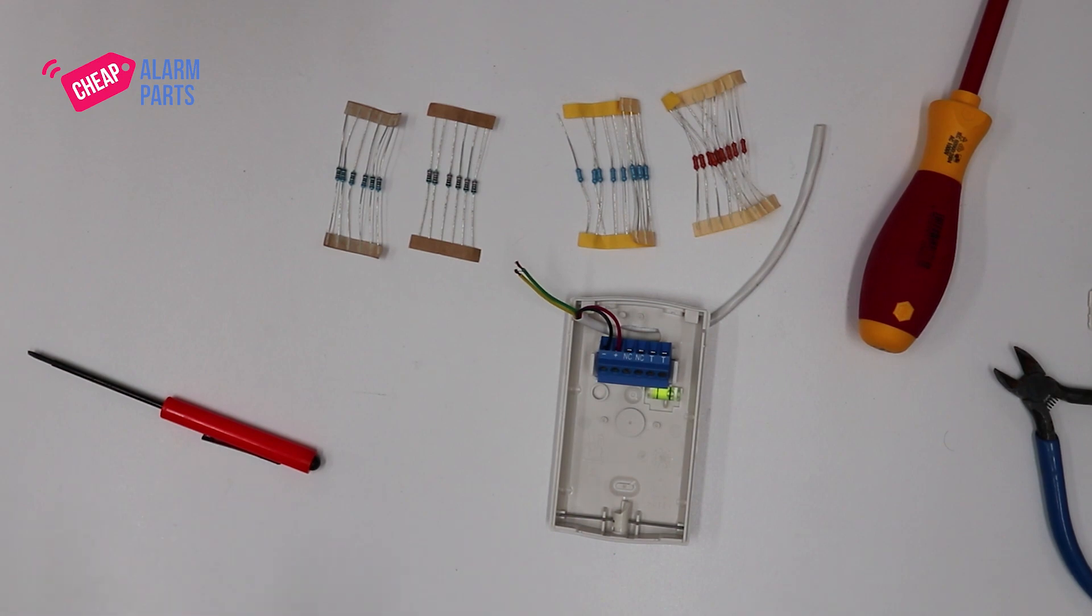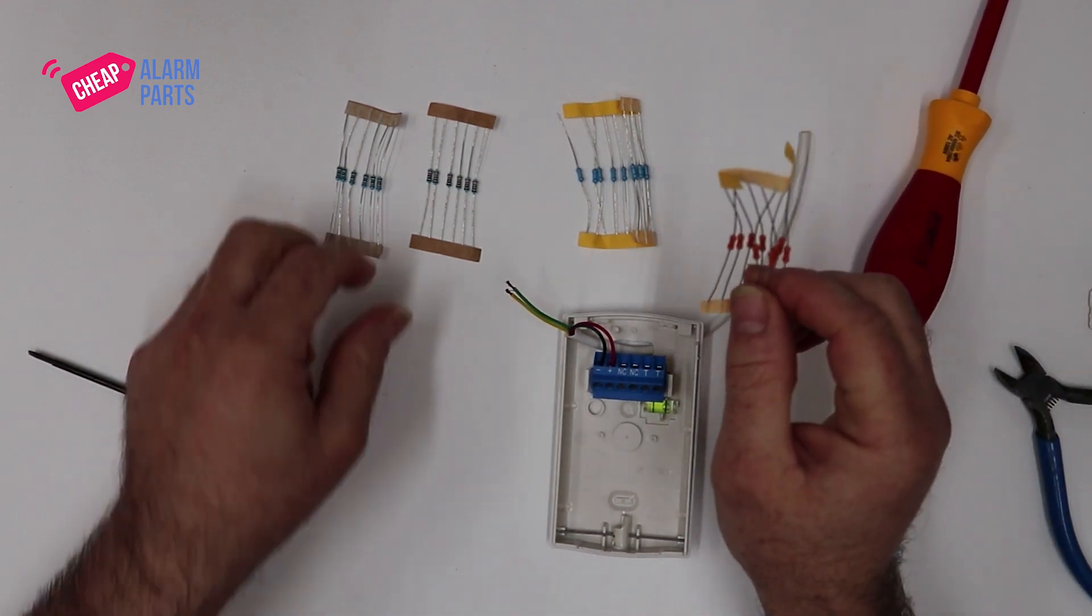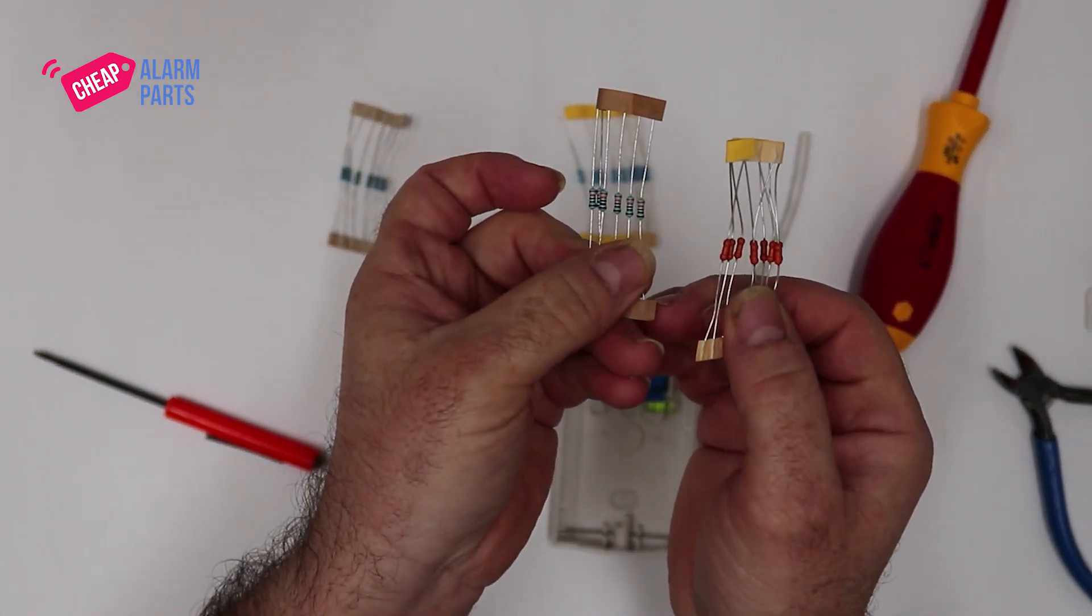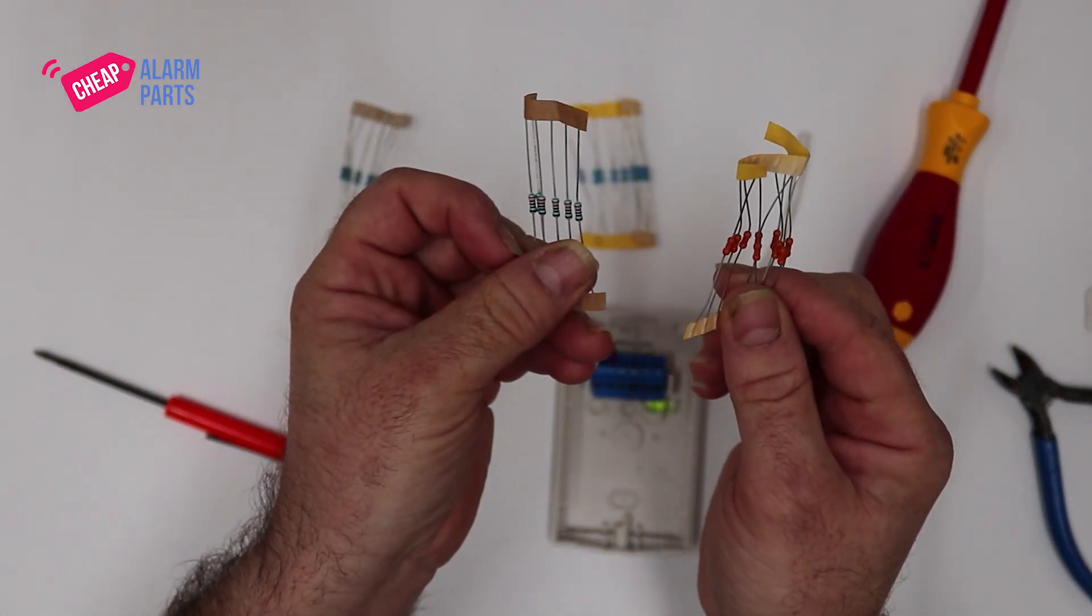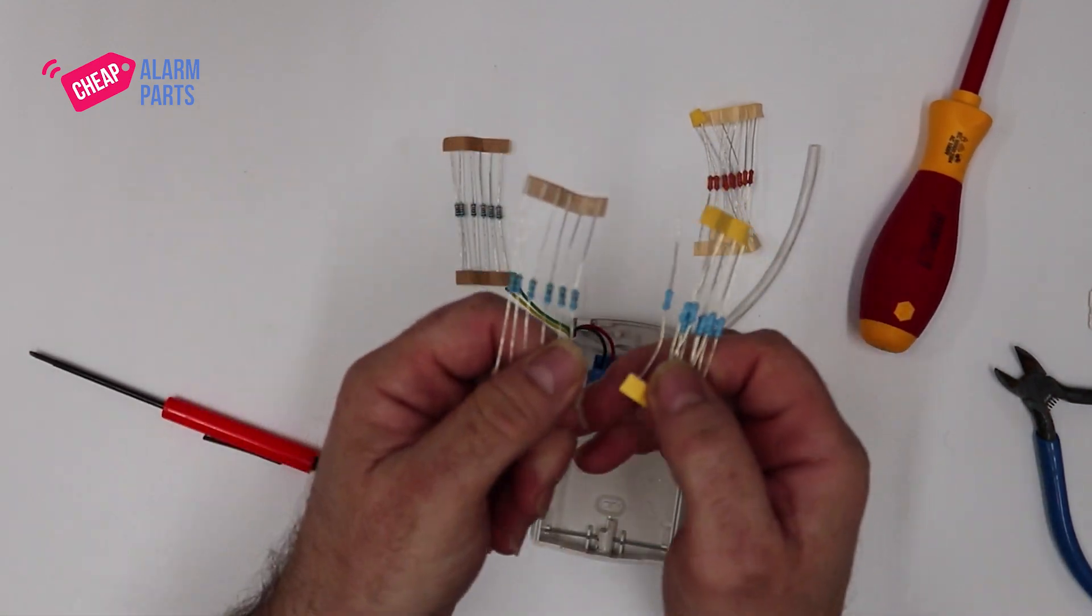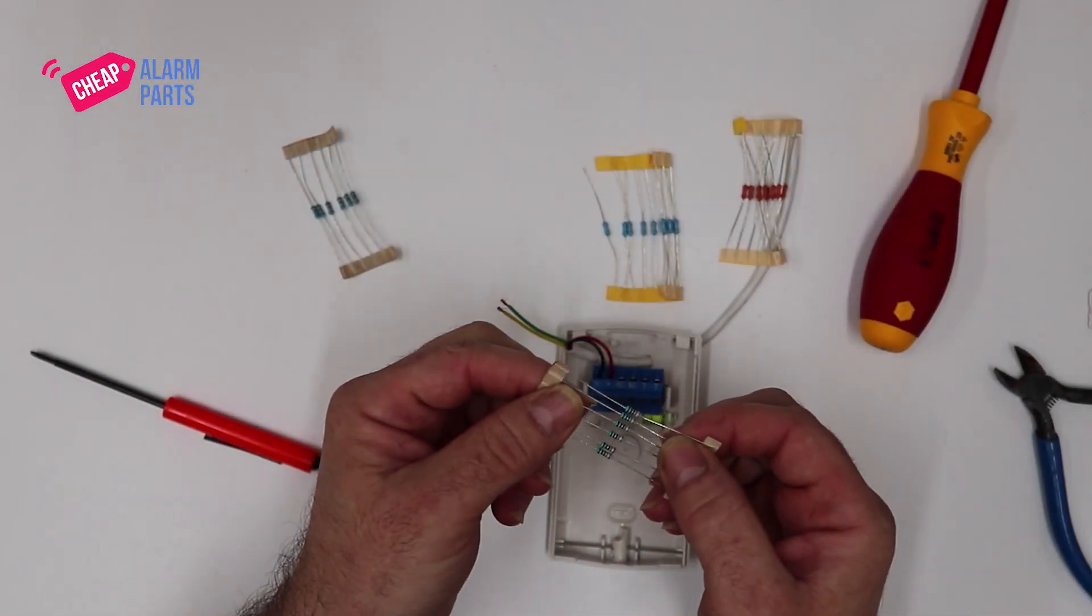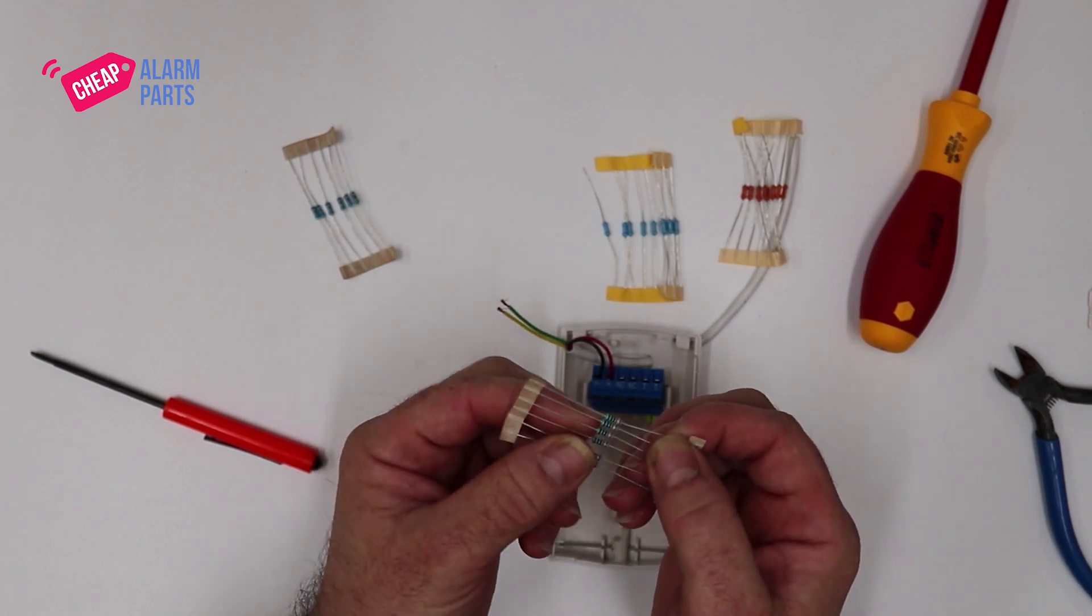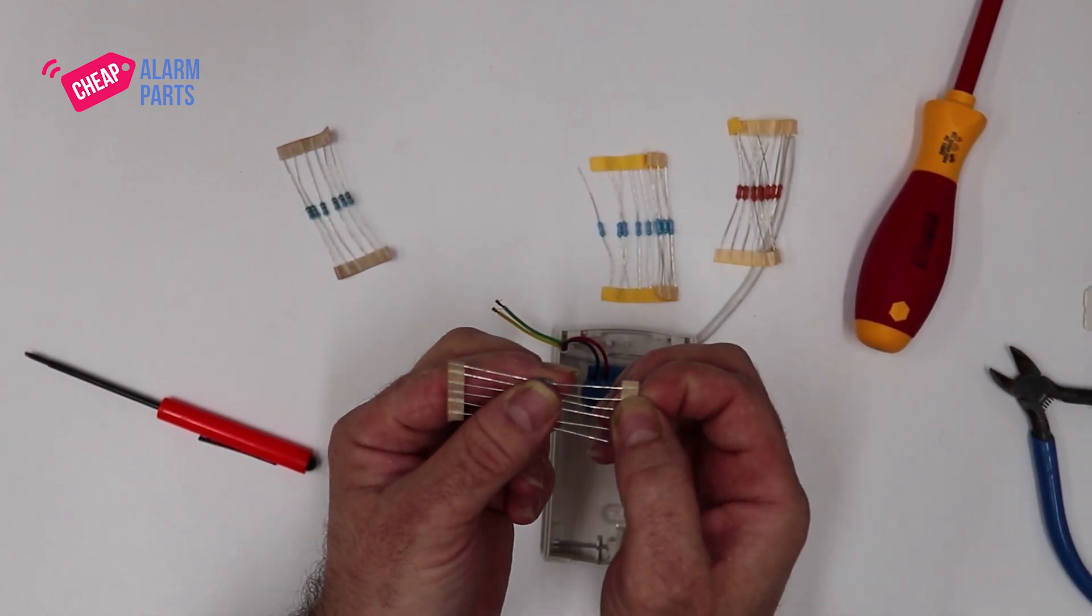So if you're connecting your detector to zones 1 to 8, we normally use the 3.3k. If you're connecting to zones 9 to 16, we use the 6.8k. It's a good idea to cut the resistor off the pack and not pull it out. Sometimes the glue sticks to the copper and it doesn't make a good contact when you put it into the sensor.